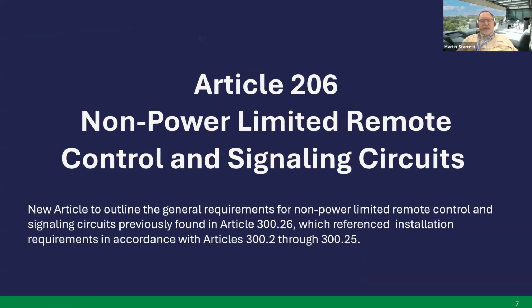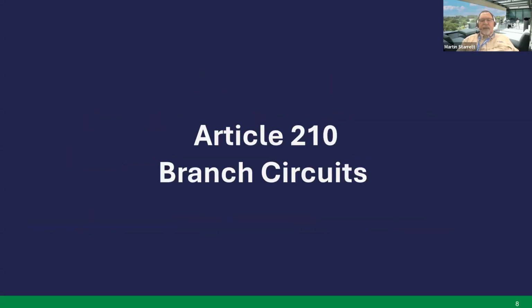Article 206, non-power limited remote control and signaling circuits, is a new article. It outlines the general requirements for non-power limited remote control and signaling circuits that were previously found in Article 300.26. In that previous article, it referenced installation requirements in accordance with 300.2 through 300.25. So now all those requirements are found in this new article. Next slide. All right, we'll get into the branch circuits, Article 210.